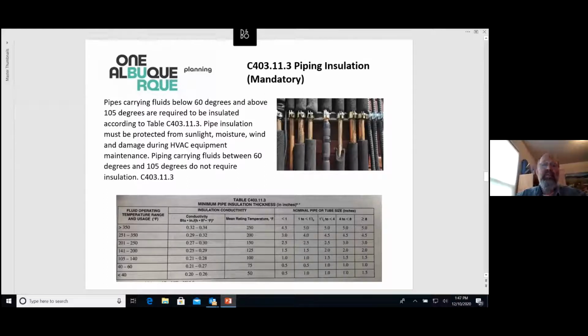The insulation will need to be protected from sunlight, moisture, wind, general damage when you're working on it. You can see some of the insulation here is torn a little. It's, you know, kind of taped up. It's getting rotten. So it's going to need to be protected from all that, because if it disintegrates and goes bad or isn't there, it's not doing anything. So just throwing Armaflex up on the roof or on a sidewall isn't so much going to cut it.